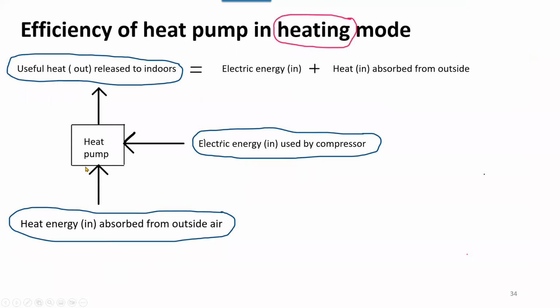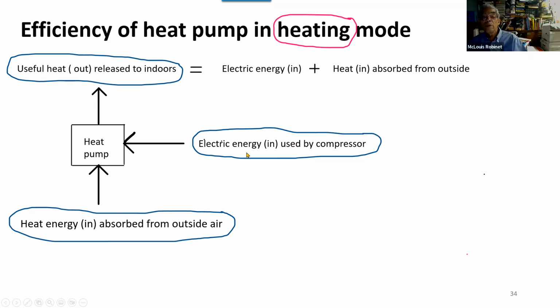Okay, so let's compare that to the efficiency of a heat pump in heating mode. Again, we pay for the electricity to operate the compressor. So this is the amount of energy we're putting in the system. The purpose of putting this energy in is to create the condition so that we can absorb energy from the sea of air or water or ground. So we have 2 inputs, what we're paying for and what we absorb. We get 1 output. That's the useful energy that's released into the indoors. Again, following the first law of thermodynamics, the input has to be equal to the output. So this plus this has to equal that. What we release indoors is what we paid for here, plus what we absorbed from the outside.